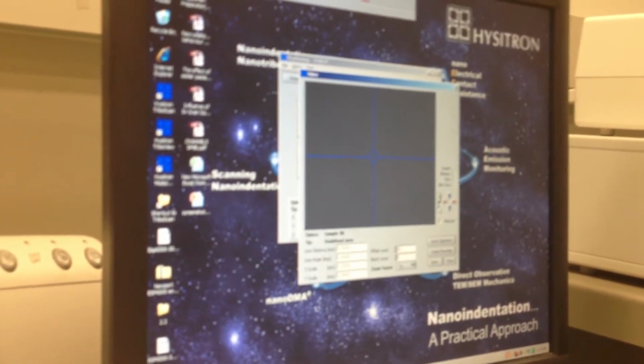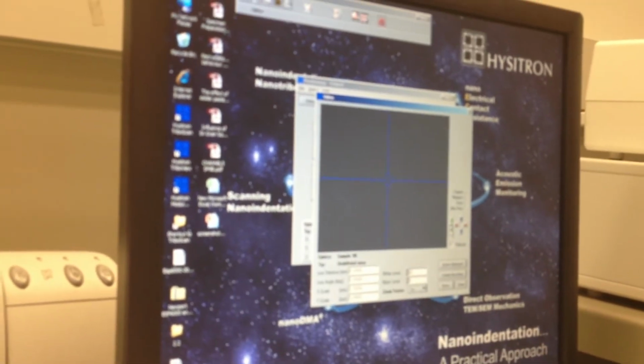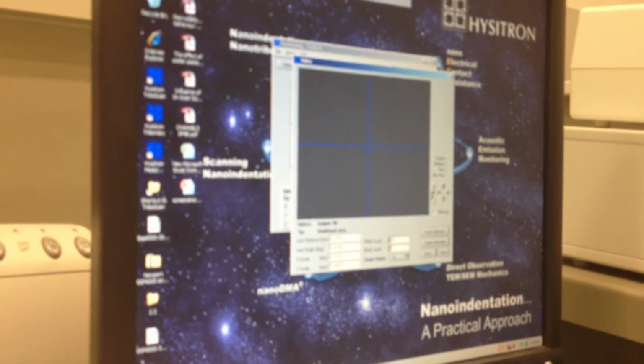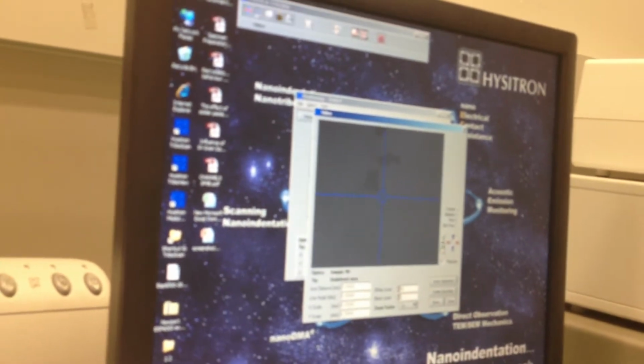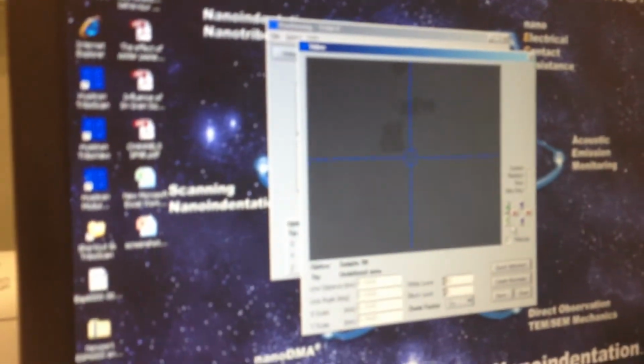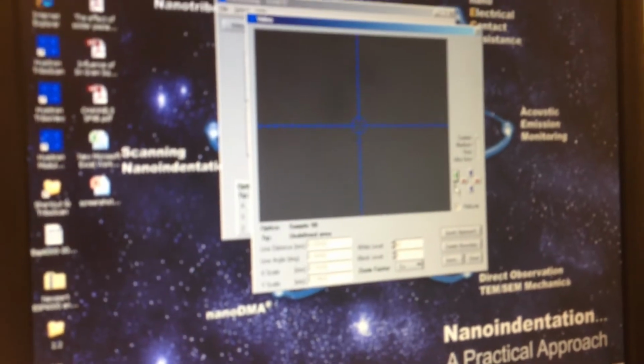The quartz is a little more difficult to focus in on, just because it's transparent. That's it right there. It's kind of tough to discern. But the easiest thing to look for are surface defects or darkened spots. And so right here, when these become a little clearer, that's when you know you've gotten a pretty good focus.